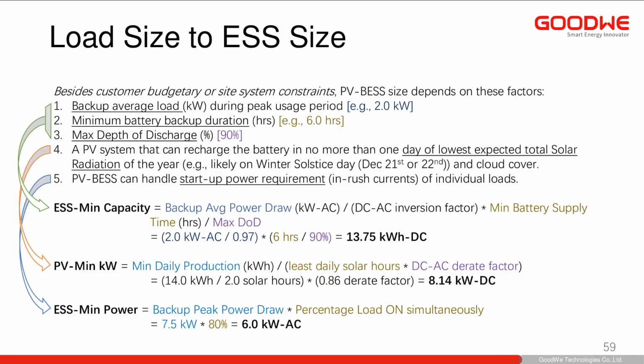All right, down to the calculations. You'll see this imagery later, so we don't need to go into detail here, but you want to calculate the minimum capacity you need for the battery, the minimum power of the PV system, and the minimum power of the ESS. You need a certain amount of power depending on whether you're backing up everything from a cold start or just switching over without loads dropping off because of a quick transfer time.